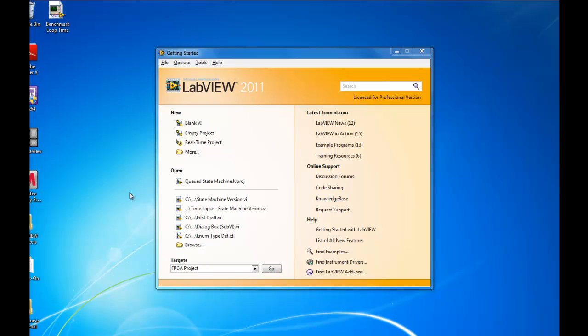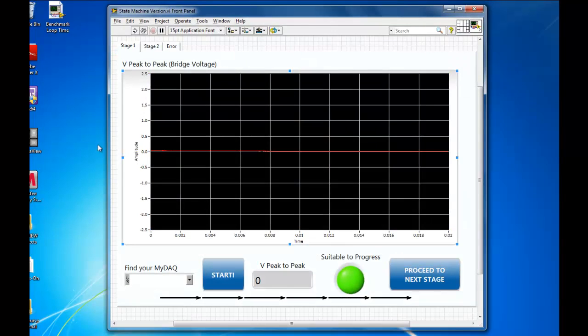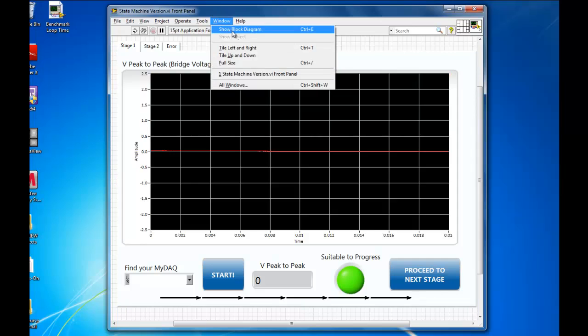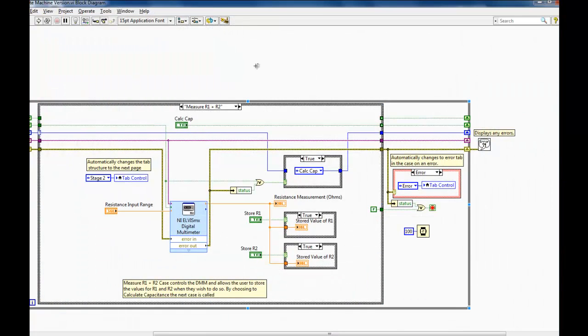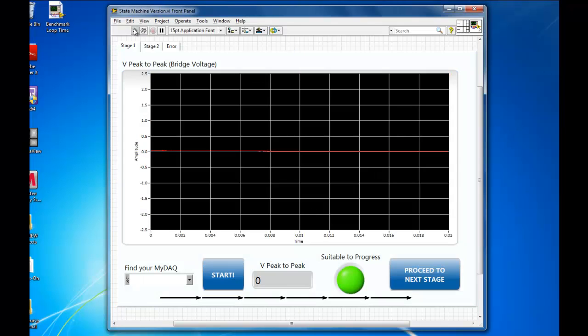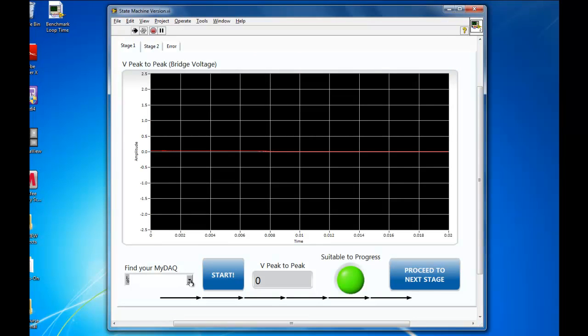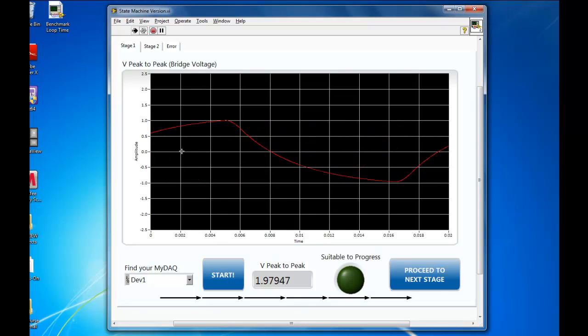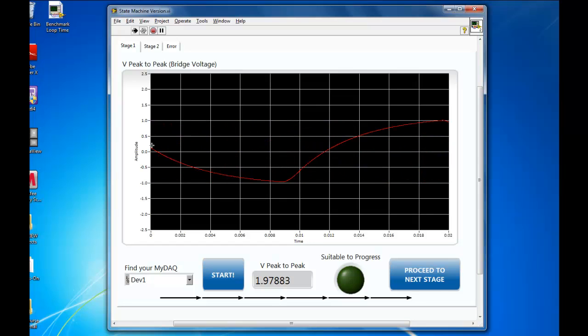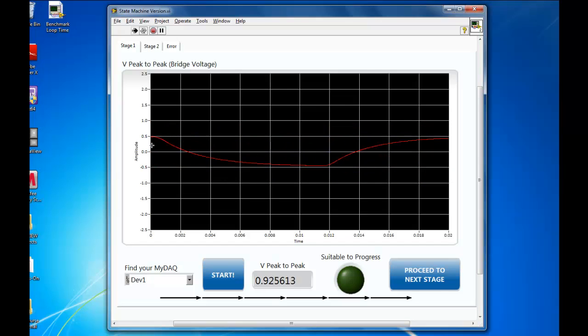Okay, so what we've got here is LabVIEW. If I open up the virtual instrument that I've put together for this, you can see the front panel which we're going to be interacting with, and similarly we could go and have a look at the code which is hiding behind there. Back to the front panel — if I just get this running, the first thing we get opportunity to do is find our MyDAQ. Mine's called DEV1, and then I can start that MyDAQ running. The trace you can see on this graph is V-peak-to-peak, that bridge voltage which we wanted to reduce to zero. So I'm going to pick up my screwdriver and start manipulating the variable resistors, twisting them about until I can reduce V-peak-to-peak essentially to zero.